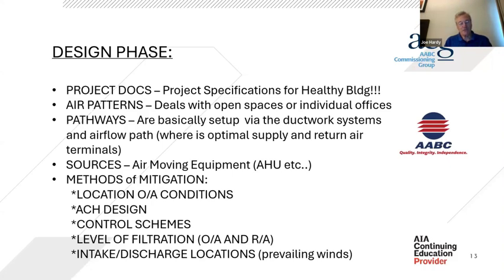We were in there testing and balancing the building while they ran a practice run with the buses. The bus happened to be parked right where the outdoor air intake for the unit was, for the space we were in. We started having our eyes water and smelling the bus fumes, wondering what was going on. Things that look minor to begin with can end up being a major issue later once you actually start occupying the building and operating your process.